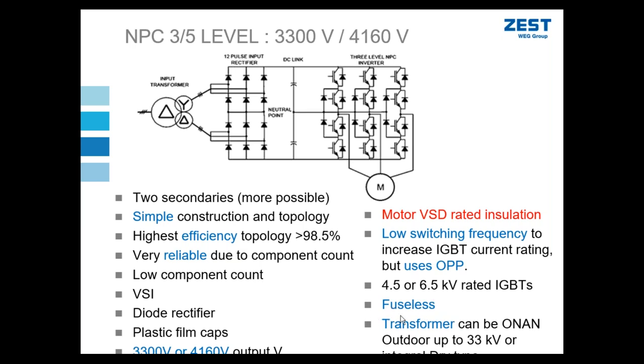This design is fuseless, doesn't have to have fuses because I do not have isolated secondaries. I have one, the VSD operates as a system. If I draw high current in any point in this VSD, it will be transmitted to the primary switchgear. Because my transformer is simple in construction, I have the option of making this topology with an integral dry type transformer or using an outdoor oil type transformer.